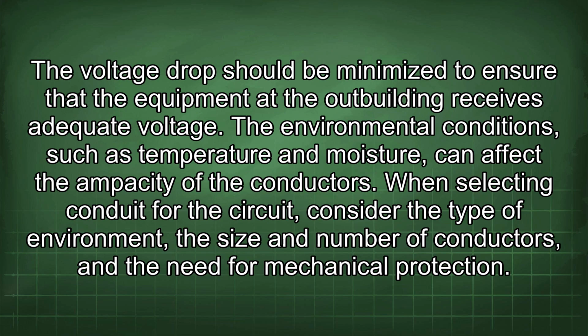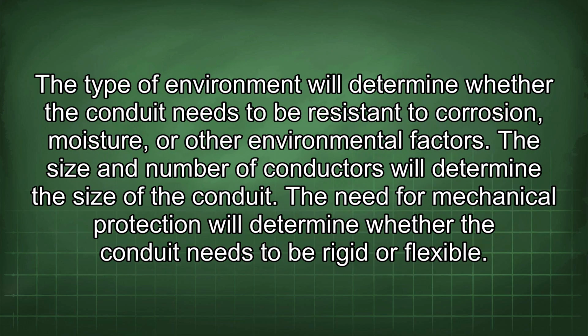When selecting conduit for the circuit, consider the type of environment, the size and number of conductors, and the need for mechanical protection. The type of environment will determine whether the conduit needs to be resistant to corrosion, moisture, or other environmental factors. The size and number of conductors will determine the size of the conduit. The need for mechanical protection will determine whether the conduit needs to be rigid or flexible.